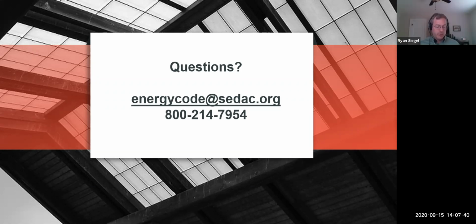We also did have someone, actually that's very good to know. One of the people attending today's webinar has brought up that Manual D is actually required under the residential code, IRC Chapter 16. So even though the energy code does not require Manual D, the residential code would require that. That may depend on which version of the residential code your jurisdiction is on, but be aware that Chapter 16 may make reference to Manual D. So thank you so much. Appreciate it, Don.